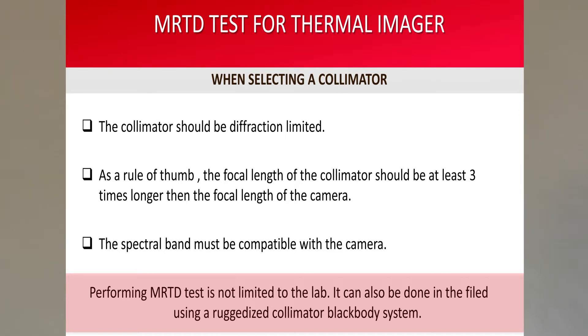For example, at CI we use mirror-based collimators with a spectral band from 0.4 to 14.6 microns. And lastly, remember that MRTD testing is not limited to the lab. It can also be done in the field using a ruggedized collimator and a blackbody system.